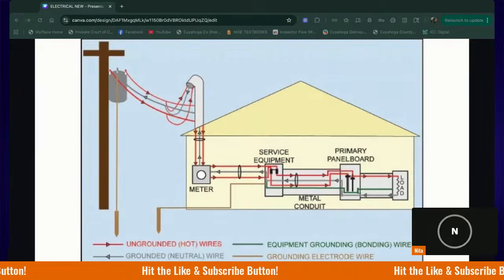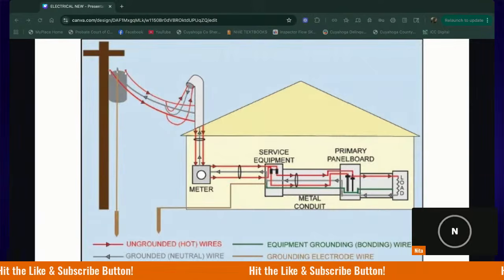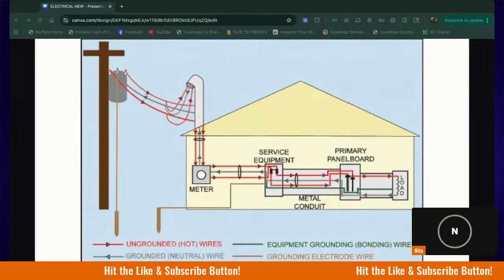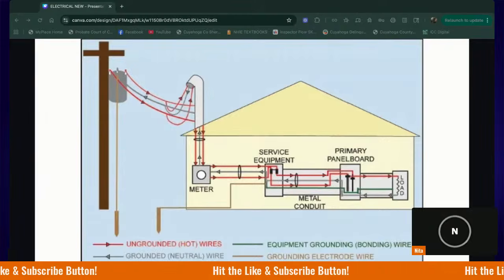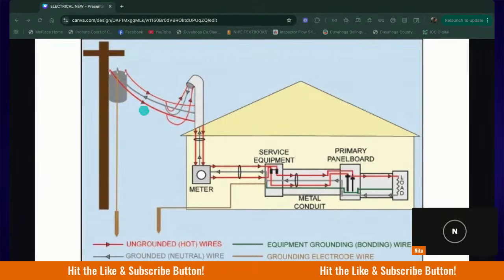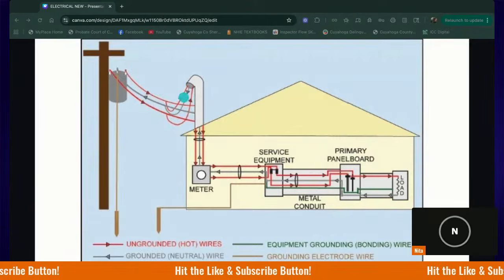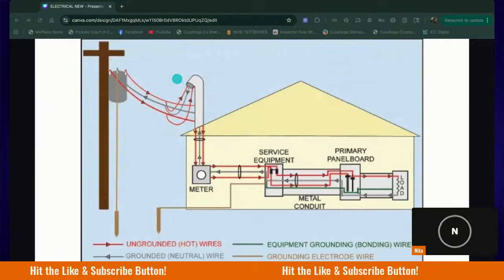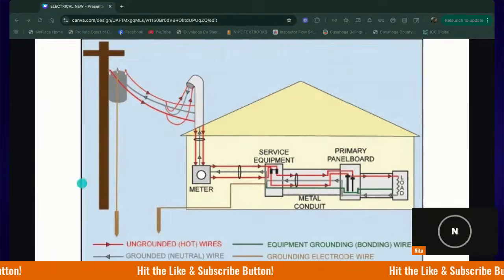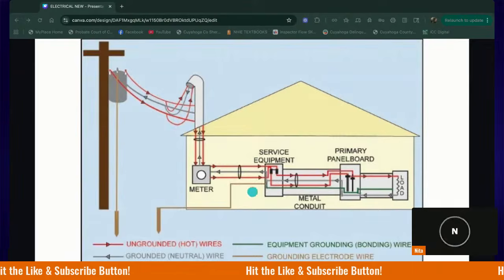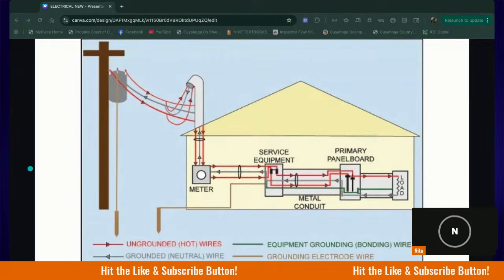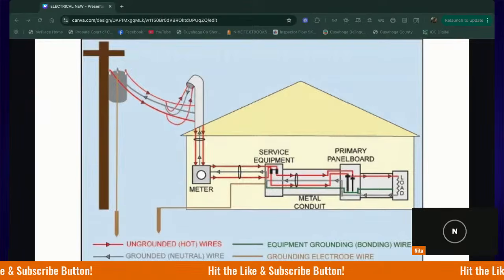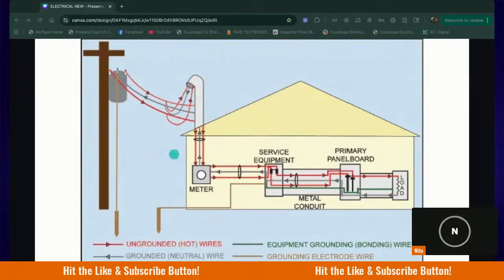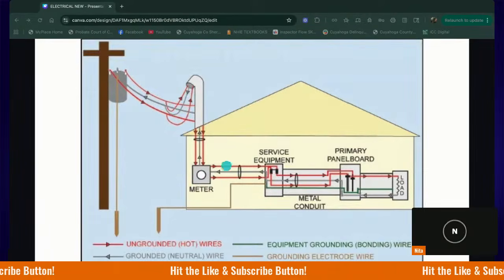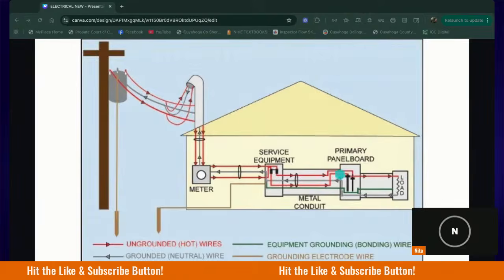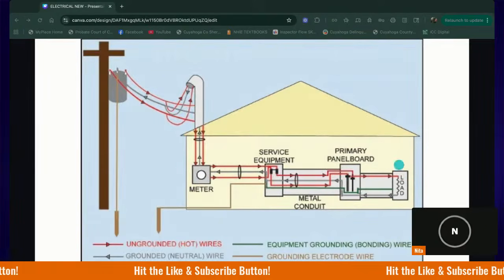Okay. So again, just one more time, we've got our transformer, our service drop if it's overhead, or our service lateral if it is underground. Our service entrance conductors, our drip loop going through our weatherhead or our gooseneck, down the service mast to the meter base, which holds the meter into the service equipment, or our panel where we have our main disconnect. The main disconnect disconnects all the power to the home. The service equipment also distributes the power throughout the house.